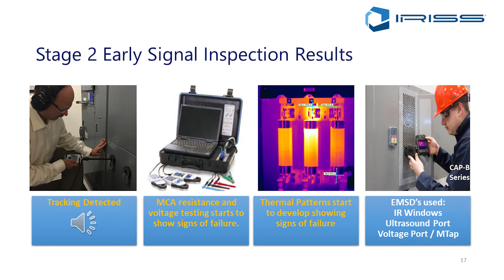Thermal patterns start developing, and other technologies too. And then lastly, if we let it go further, we could get to the point where we've got full-blown arcing going on. Now we've got an intermittent path to ground for energy. It's not a full-blown bolted fault, but it's going to be if we leave it. So let's be careful—again, thermal patterns get more distinct.